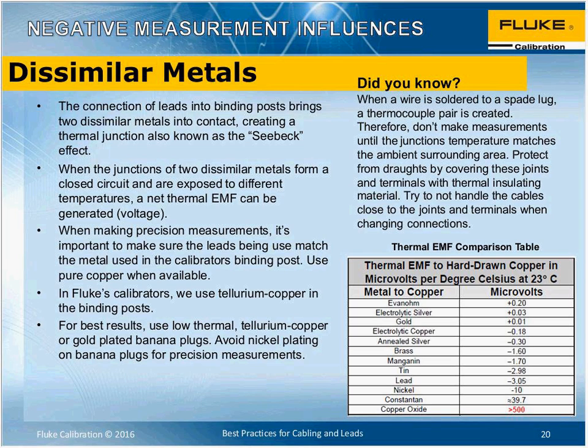So we avoid any of these junctions of dissimilar metals that could be, for example, when we have two different metals joining together because our leads have to terminate into the banana jack, or they have to terminate into the spade lug. That spade lug then has to connect onto the terminal and so on. So there are junctions there, and by choosing appropriate materials for our leads, we can avoid those dissimilar metal junctions, which is why in the calibration instruments we provide from Fluke, we use tellurium copper, which is one of the lowest EMF generating metals. You see there's some examples on the right hand side there.